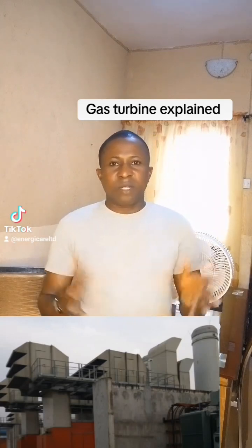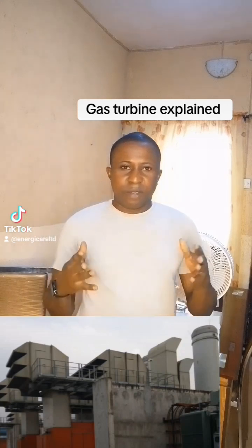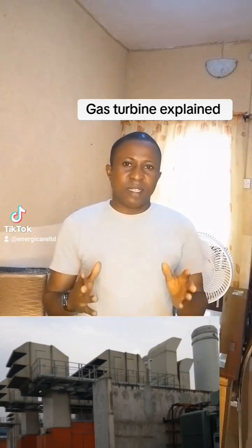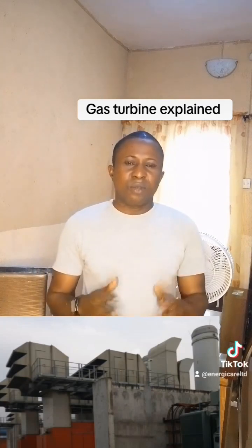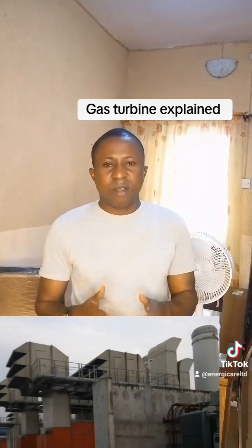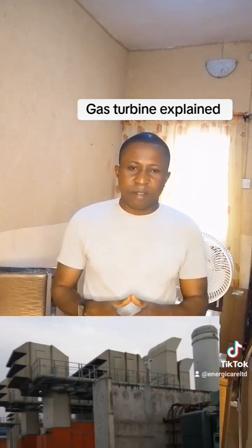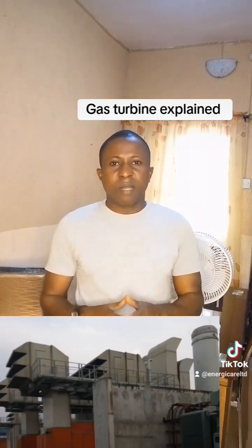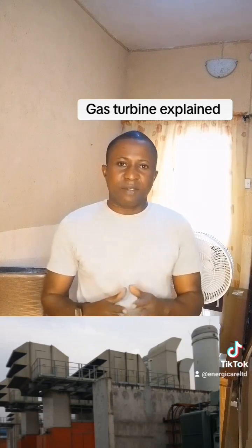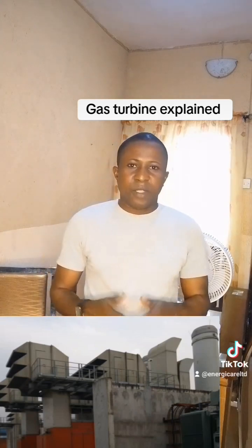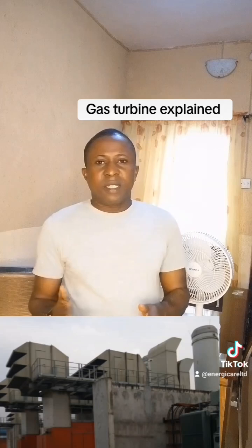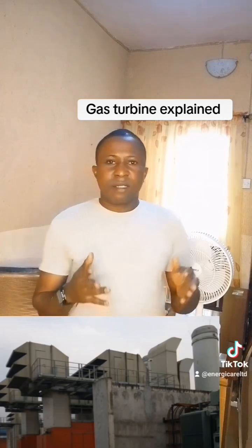There are some locations that are very dirty. If your turbine is situated around such an area, you know you are going to do frequent washing of your pocket filters. If not, your turbine will be shutting down on high differential pressure. So this is the air filtration system.